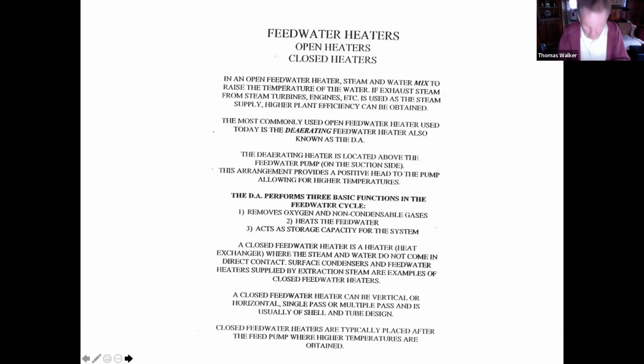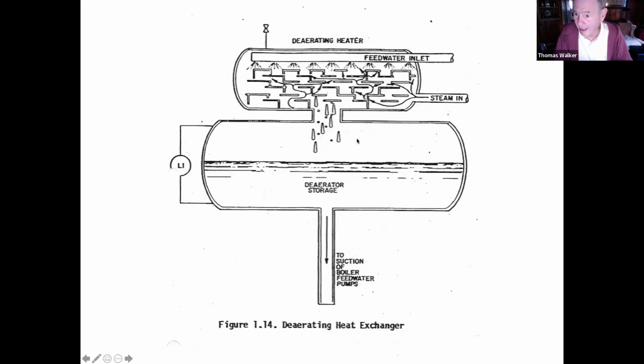For tonight's lesson, there's a couple of pieces of equipment in the boiler room that are so standard they're actually in every single plant. The first one is what we call an open feed water heater. The definition of an open feed water heater is this: the steam and water mixed together. They come in direct contact. The only type of open feed water heater that we use today is known as a deaerator, or DA for short. In a typical DA, the water going into the DA is typically condensate returns. The condensate returns are coming back from the plant.